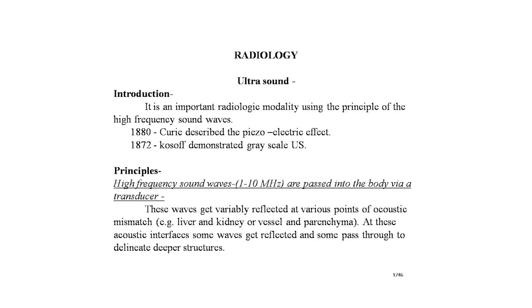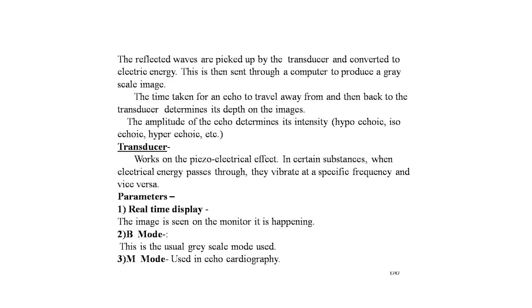These waves get variably reflected at various points of acoustic mismatch — for example at the liver and kidney interface, or vessels and parenchyma. At acoustic interfaces, some waves get reflected and some pass through to delineate deeper structures. The reflected waves are picked up by the transducer and converted to electrical energy, which is sent through a computer to produce a gray scale image. The time taken for an echo to return determines its depth.